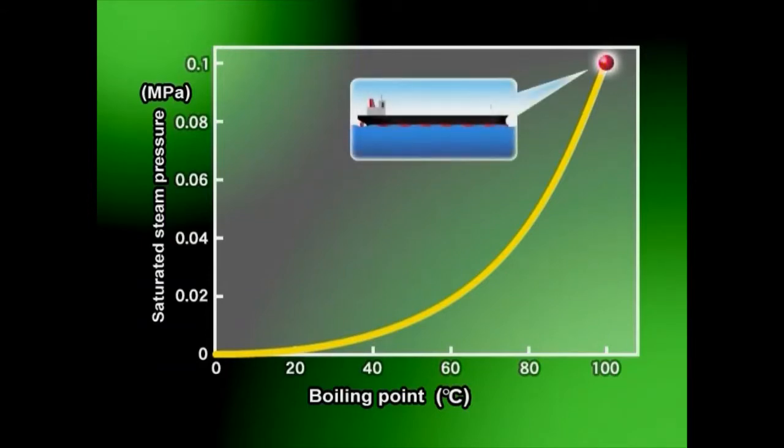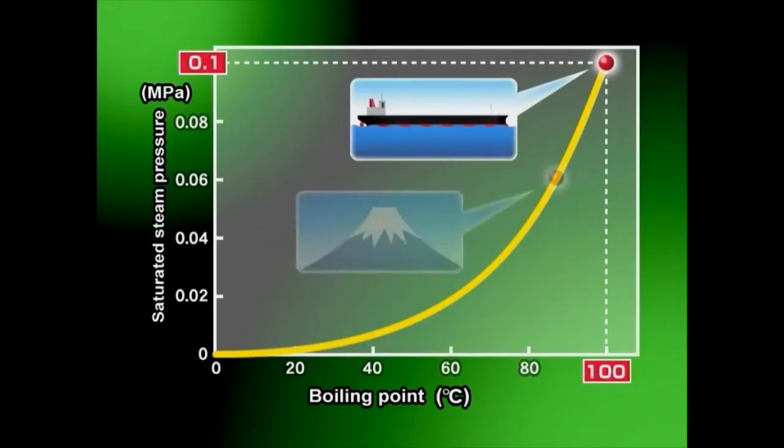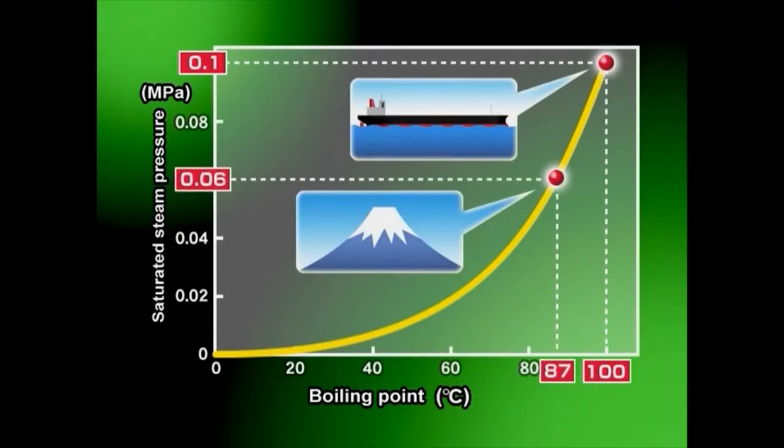Water boils at 100 degrees Celsius under one atmosphere, or 0.1 megapascals. But on top of Mount Fuji, the atmospheric pressure drops to 0.06 megapascals, causing water to boil at 87 degrees Celsius. As a result, the critical pressure at which a liquid begins to boil under a certain temperature is called saturation vapor pressure for that temperature. The lower the saturation vapor pressure, the lower the boiling point. In other words, vapor bubbles in cavitation occur where water pressure is low.